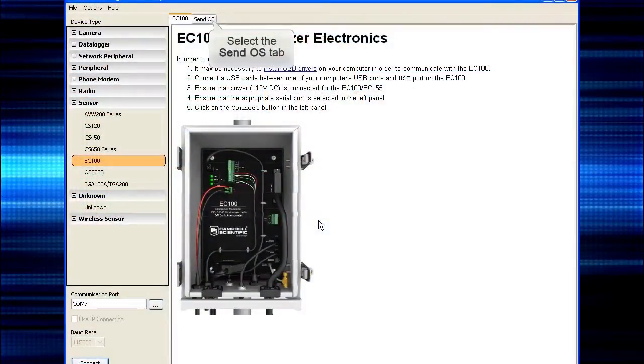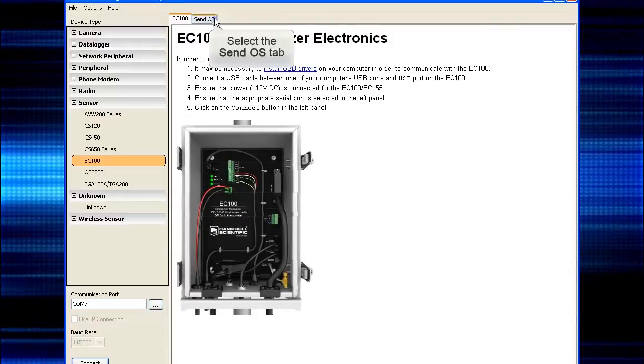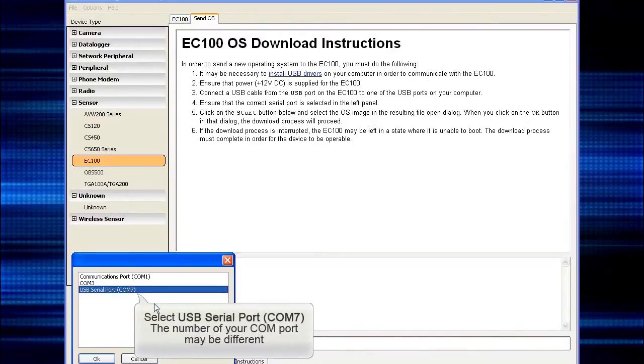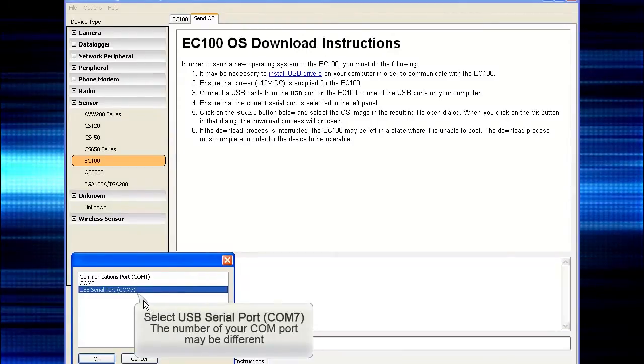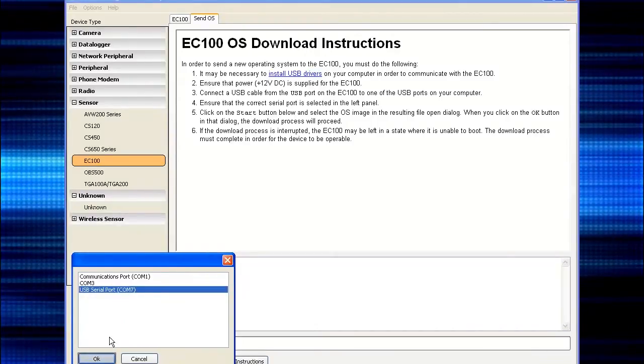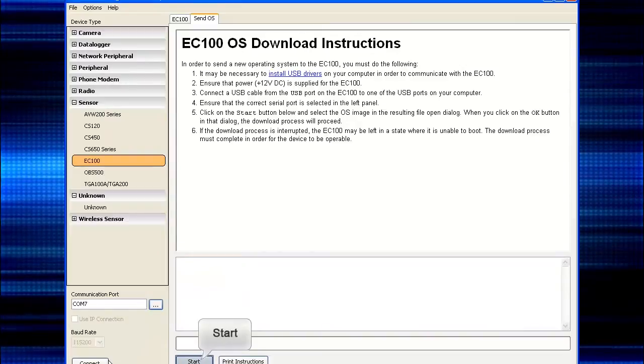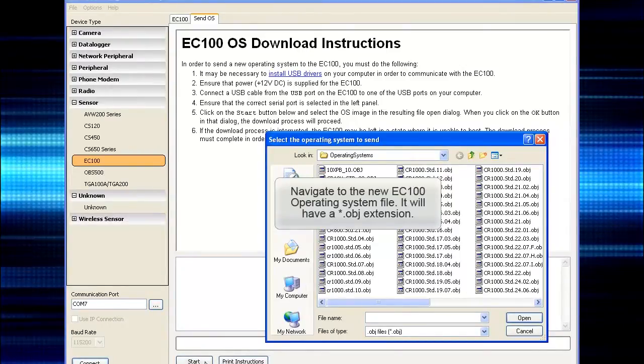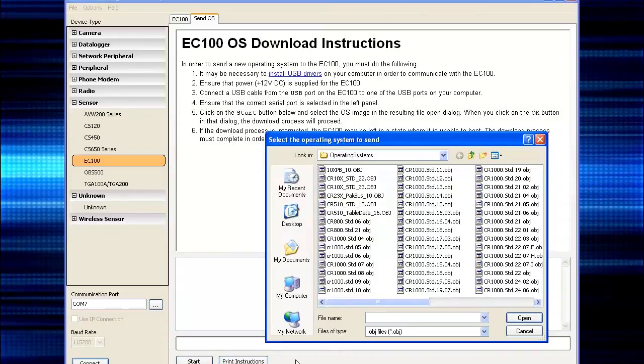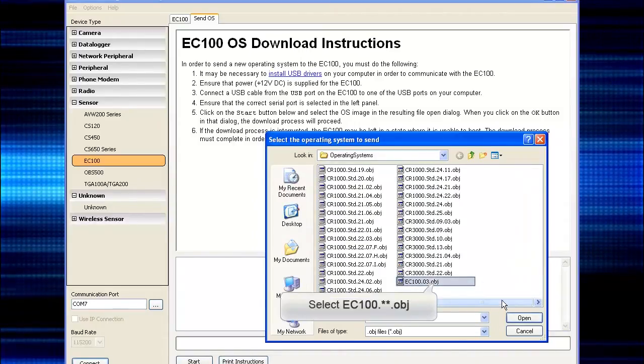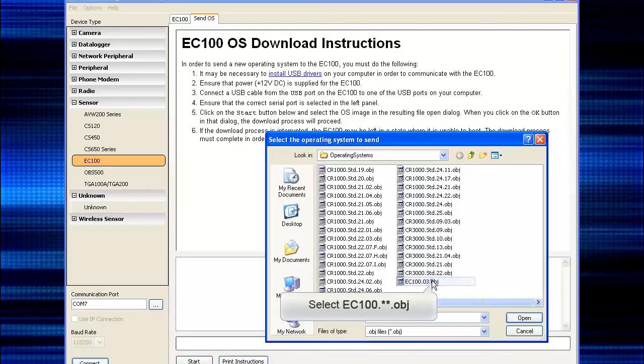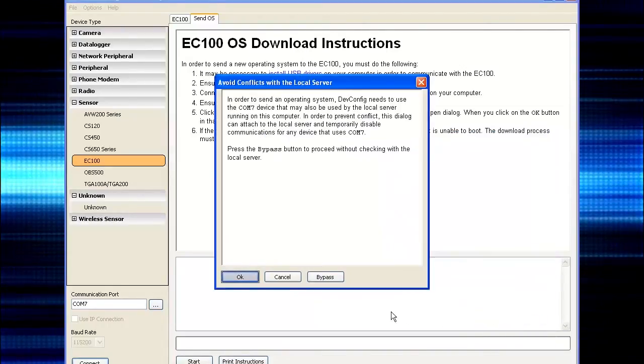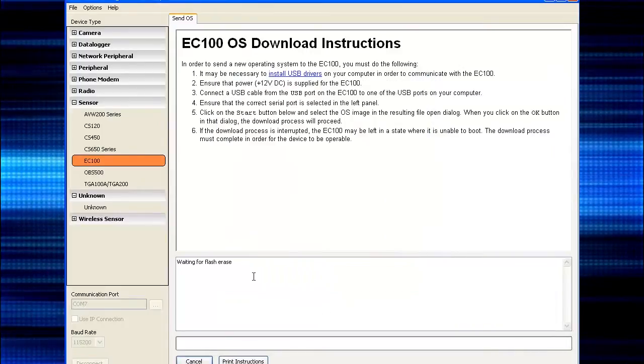From the device configuration utility, click the 'Send OS' tab. Click the dot-dot-dot button in the lower left and navigate to the USB serial port we just installed. Mine says COM7 — your COM port number may be different. Click OK. Click the Start button and navigate to the new EC100 operating system. It will be in the CampbellSci lib operating systems folder and have a .obj extension. Select it, click the Open button, then click OK to avoid conflicts and wait while the operating system loads.